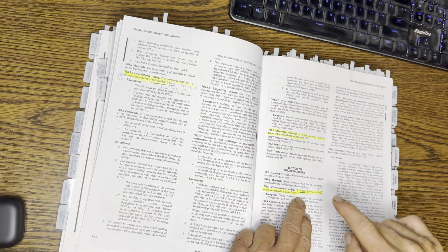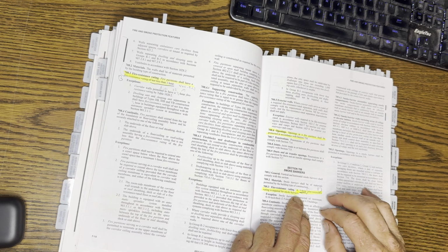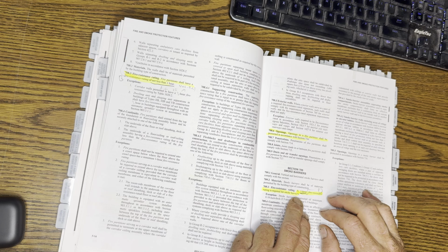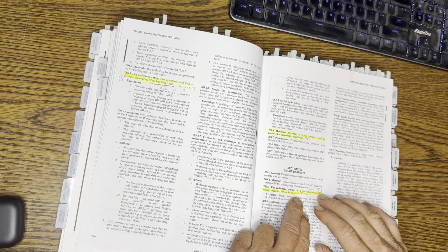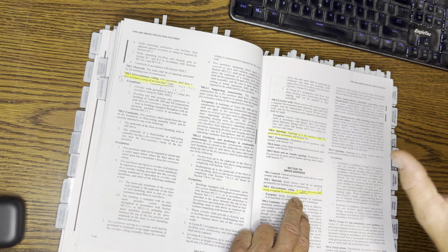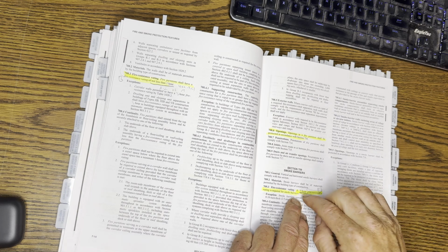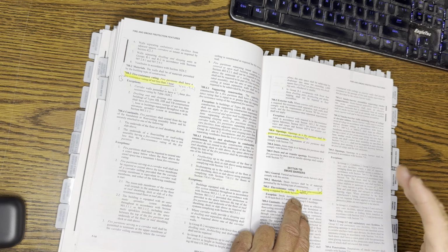I want to be very clear, 1, 2, 3, 4 hour does not correspond to real life survivability. This was developed back in 1918. What the heck was his name? It's on the tip of my tongue, but 10 years after the guy that developed this in the early 1900s, he says, look, we had to come up with something. What it is is basically a furnace that uses natural gas, and it ramps up the heat over time, and then you're measuring how fast temperature moves through a product.